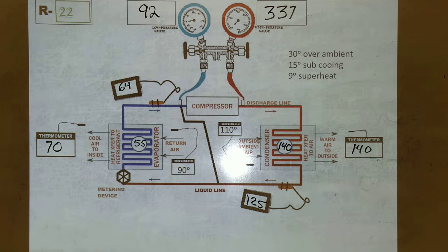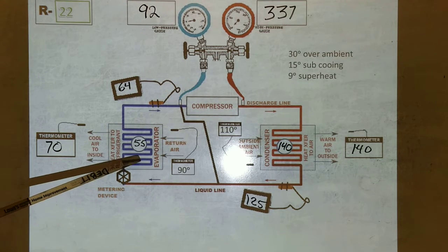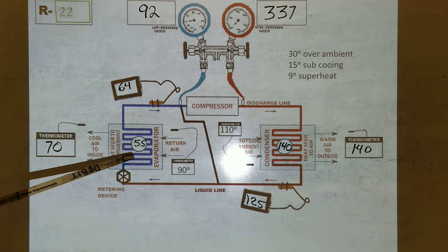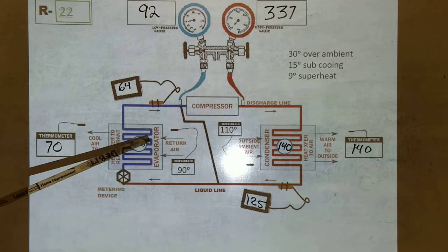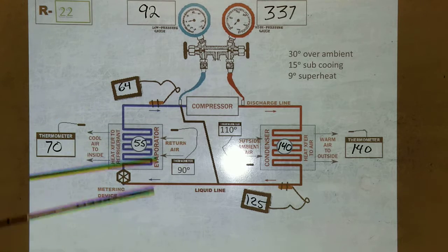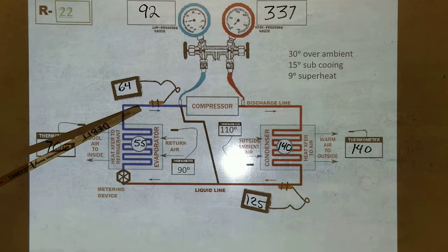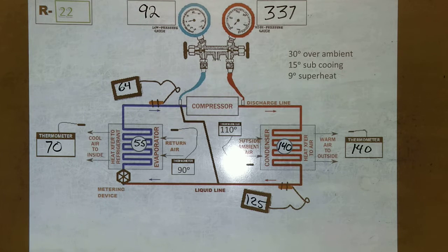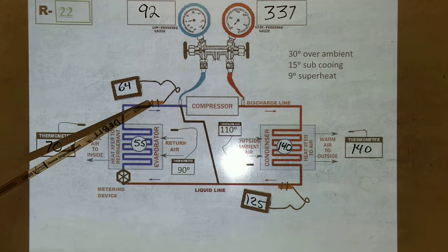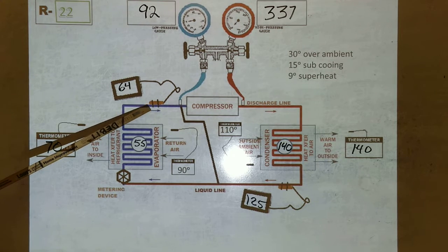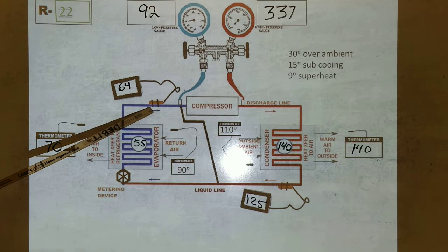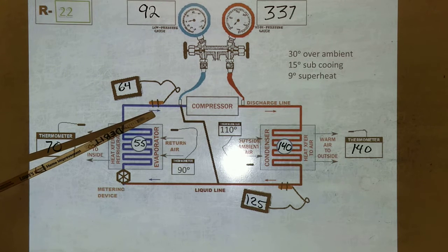Now, in order for you to understand why subcooling and superheat are important: if this temperature right here contains liquid and vapor, okay? Because that's where it's changing state. That's where the refrigerant is changing from a liquid to a vapor, right? So we wanna make sure that in the suction line, before it gets to the compressor, it's 100% vapor. If we had 55 degrees right here, what's that telling us? Everybody all at once, in unison this time. What is it telling us? There's still liquid in this. And that's bad.